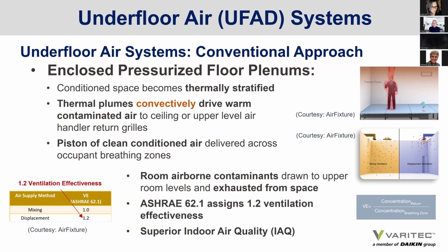The enclosed plenum pressure, again, results in thermal plumes. Wherever there's a heat source or surface temperature greater than the room set point, a thermoconvective plume results, drawing cool, conditioned air across the breathing zone, while that thermal plume will remove contaminant warm air to the upper levels of the space where it's exhausted from the room. And it's because of that thermal plume and its efficient removal of contaminants from the occupied zone that ASHRAE has assigned a 1.2 ventilation effectiveness to these thermally stratified environments, including underfloor air systems.